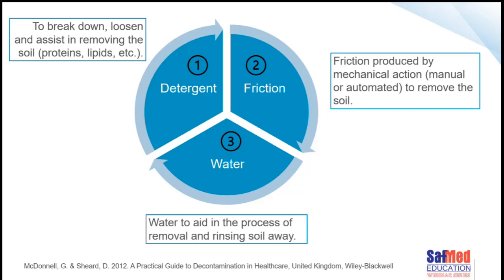Friction itself is produced by a mechanical action, and that action can come from rubbing, scrubbing, or brushing manually, or from mechanical action like the force of water you'd get in an automated washer disinfector, or the bubbles formed in an ultrasonic cleaner. That's the mechanical action component of creating friction.